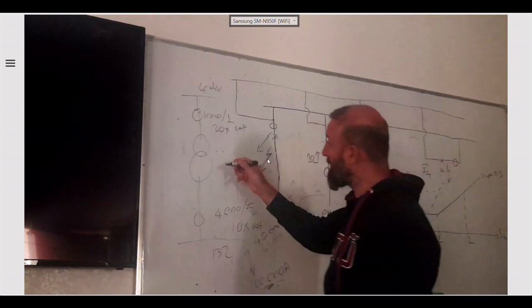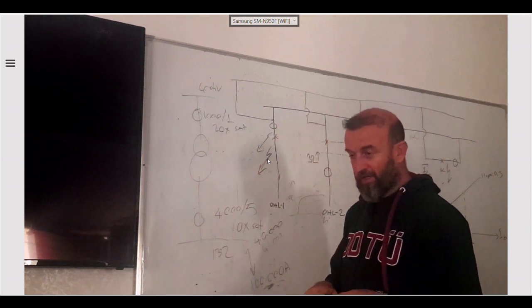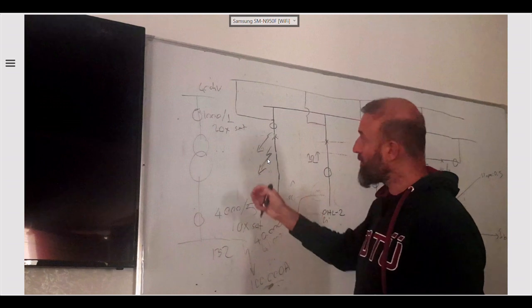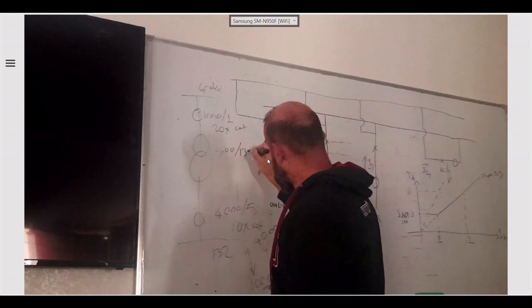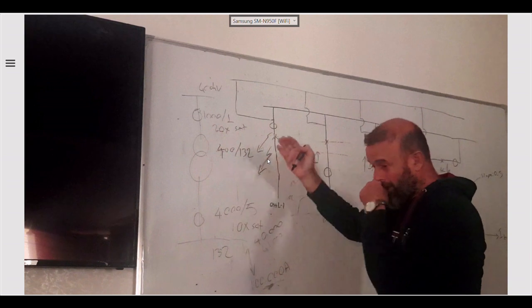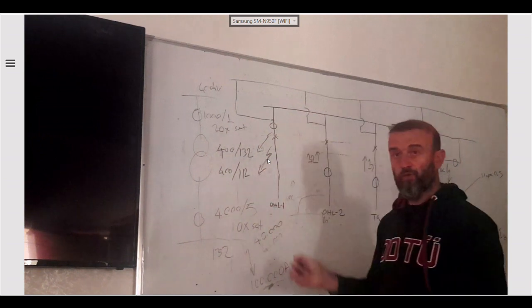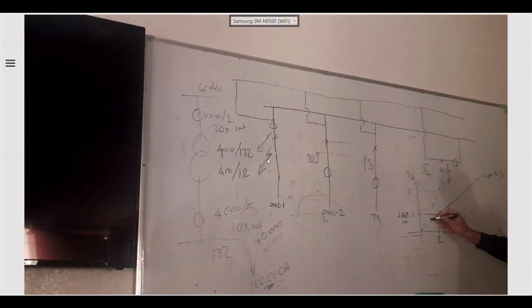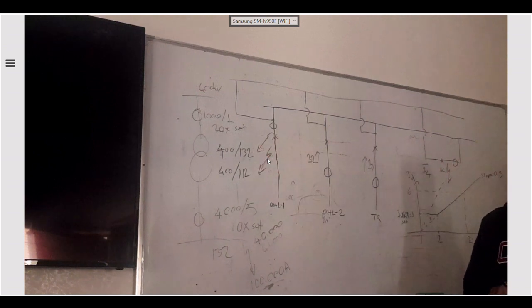Yes. And also, assume that we have an on-load tap changer. In the normal case, what we define is to make it for the central tap position, and in the central tap position, this translates perfectly with the ratio, 400 over 132. This is the perfect case. But if we have too many taps, and the tap position is changed, it may even be like this, a 20 kV difference is available here. So the current will already be somewhere here. So we have to define some values by considering those parameters, tap position and CT saturation.